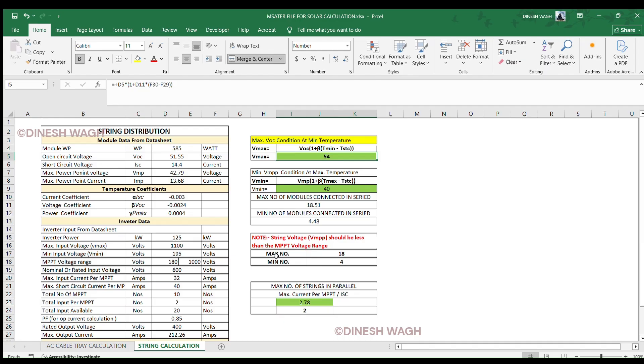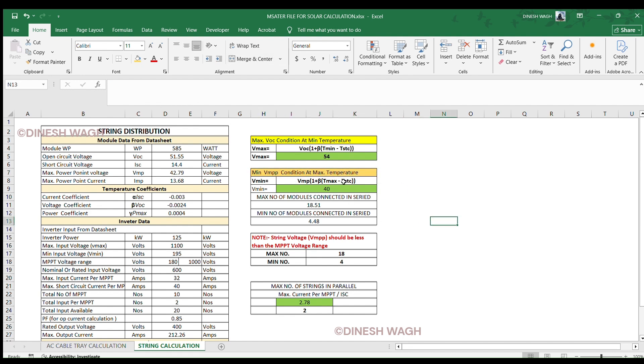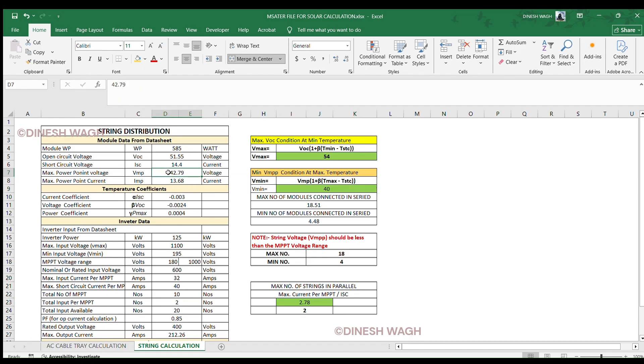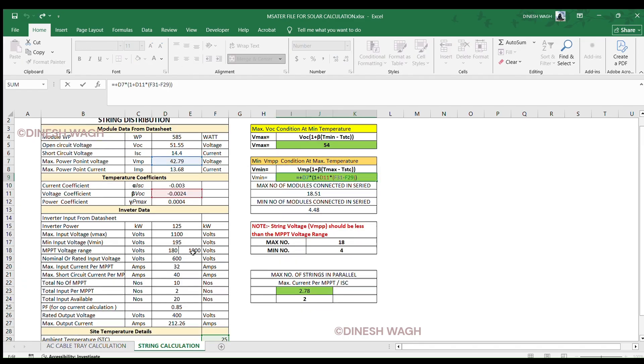Now V_min at high temperature: V_min = VMP × (1 + beta × (T_max − T_STC)). Putting in values: 42.79 × (1 + (−0.0024) × (50 − 25)) = 40 V. So V_min is 40 V. This ensures we never go beyond inverter limits due to temperature changes.